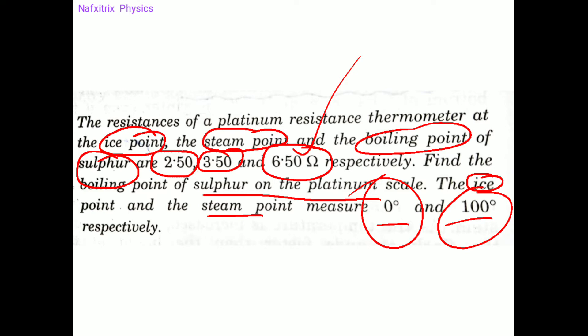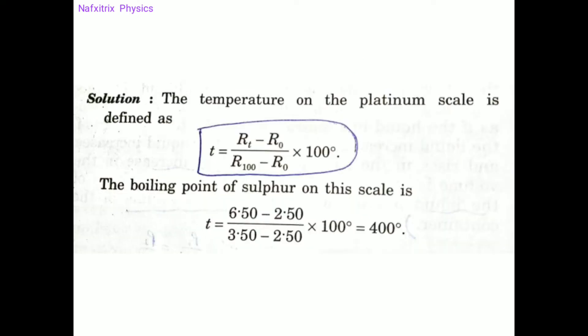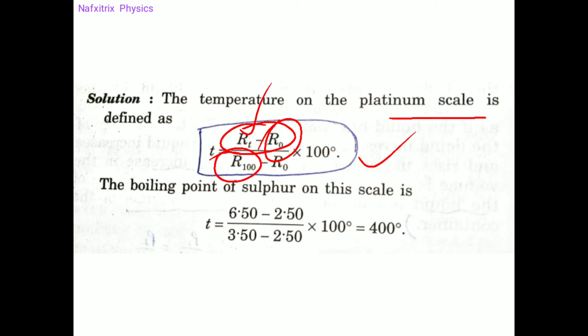The formula for temperature on the platinum scale is: T = (R_T − R_0) / (R_100 − R_0) × 100, where R_T is the resistance at temperature T, R_0 is the resistance at the ice point, and R_100 is the resistance at the steam point.